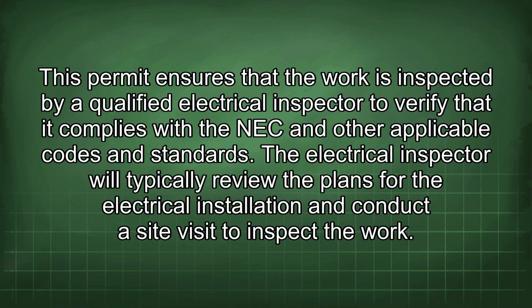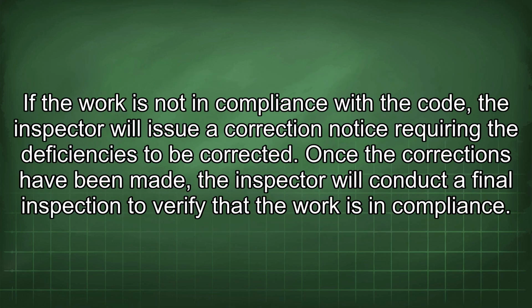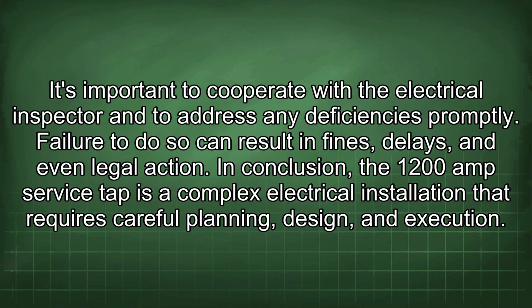The electrical inspector will typically review the plans for the electrical installation and conduct a site visit to inspect the work. If the work is not in compliance with the code, the inspector will issue a correction notice requiring the deficiencies to be corrected. Once the corrections have been made, the inspector will conduct a final inspection to verify that the work is in compliance. It's important to cooperate with the electrical inspector and to address any deficiencies promptly. Failure to do so can result in fines, delays, and even legal action.